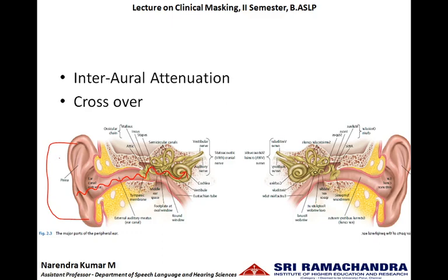But as the intensity of the sound increases, the vibration amplitude of the diaphragm also increases. At a particular intensity level, the amplitude of vibration of the diaphragm in the transducer is great enough that it can induce the vibration of the encasement of the transducer. So the whole transducer starts to vibrate. As the transducer is placed against the head, this vibration can induce bone conduction hearing.